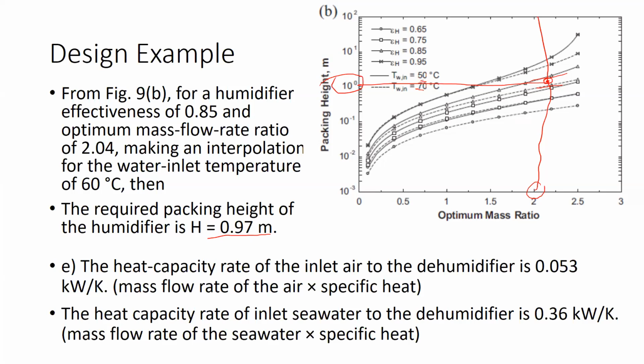So 25 centimeters on the top to put a shower head or any sprayers for distributing the water. And at the bottom, it will be sort of a small tank that collects the brine before you take the brine out. Now, the next step, now we have sized the humidifier. The dimensions are going to be 25 centimeter by 25 centimeter, and the height should be somewhere higher than 1 meter. So that is going to help us to size the unit.